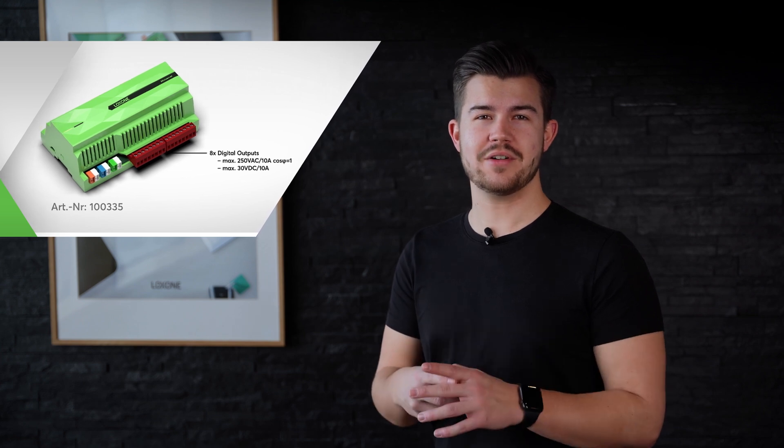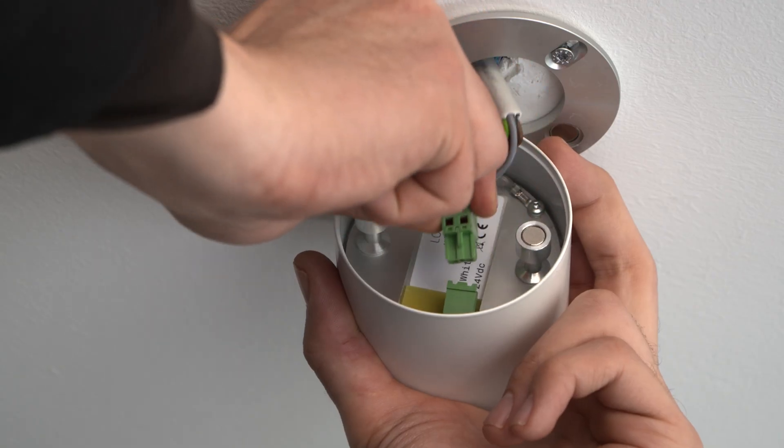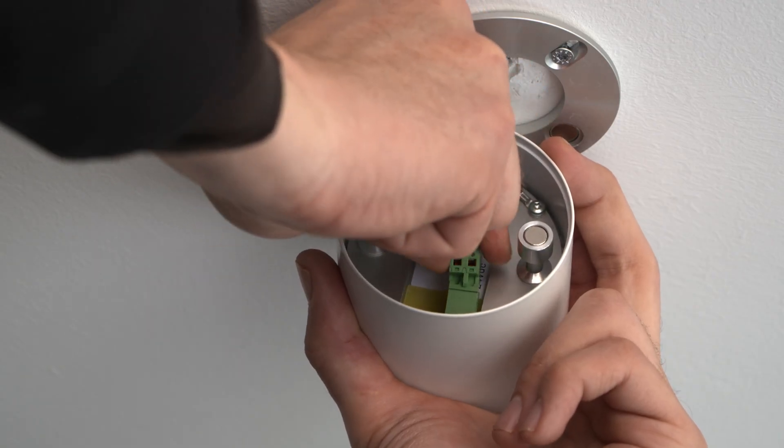However, bear in mind that with relays, customers' comfort levels will be affected, because the lights only have on and off functionality. And also, extreme caution is required when switching LED lamps via a relay. This is because inrush currents of LEDs can exceed the actual rated current up to 100 times, which can lead to an overload of the relay.